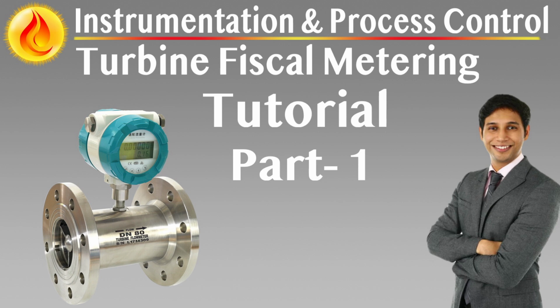Each turbine meter must undergo initial calibration against a recognized standard meter. The result is a performance footprint that includes calibration factors and full geometry verification. This initial fingerprint acts as the reference for future proving and diagnostics. Any future deviation from this footprint must be investigated, documented, and approved before system recommissioning. The fingerprint protects the meter's identity and confirms whether shifts in measurement are due to aging, fouling, or mechanical degradation.